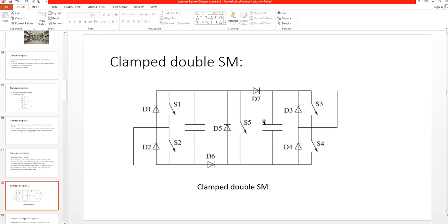The arm current is divided between two capacitors which are in parallel, so the inserted voltage against the fault current is half of the DC side voltage. In case of a pole-to-pole fault on the DC side, the whole DC voltage is available for blocking fault current flowing from one phase on the AC side through the DC side and back to another phase.